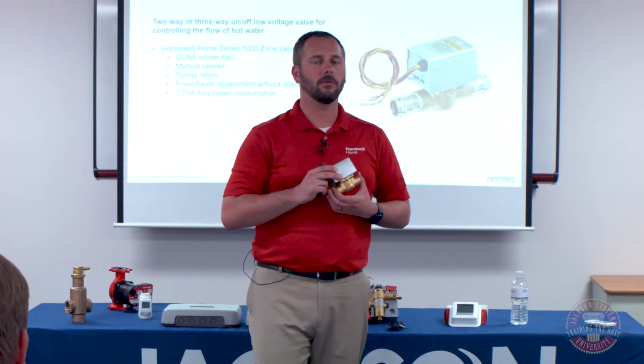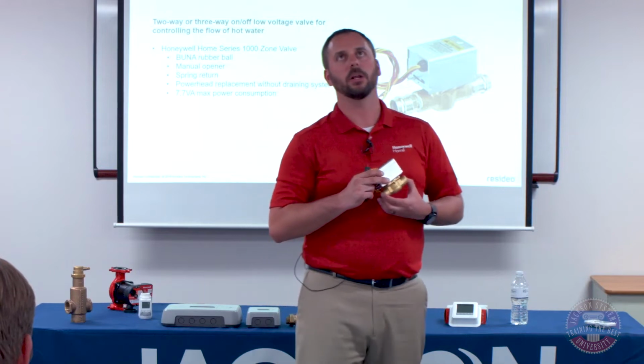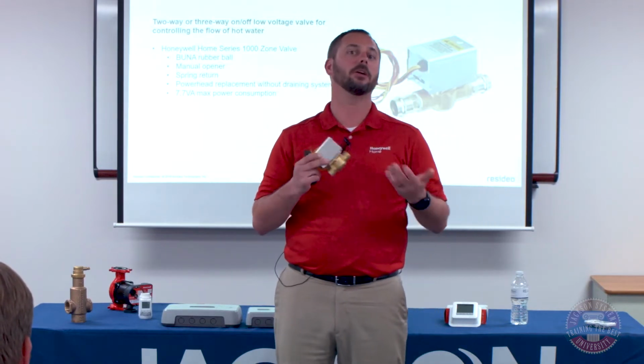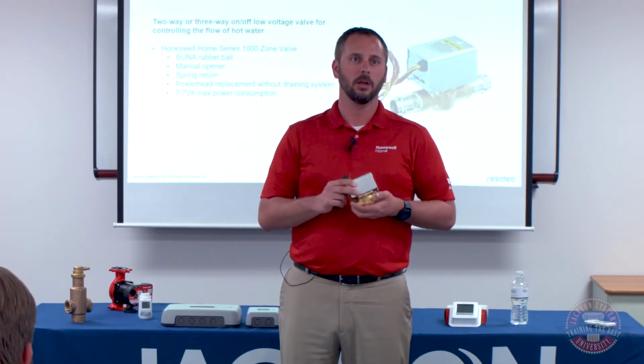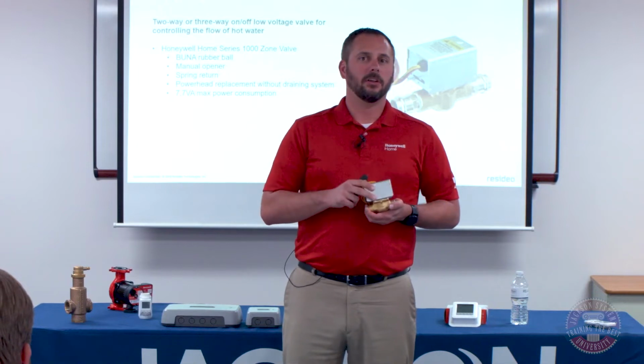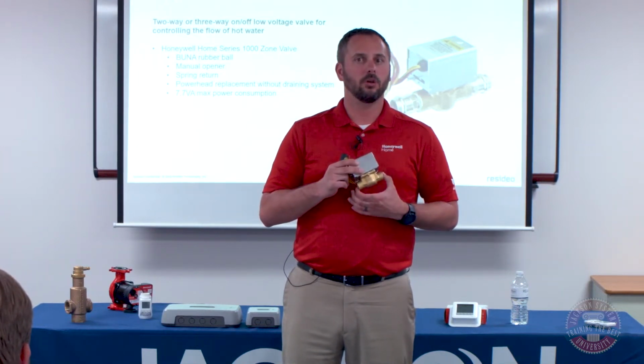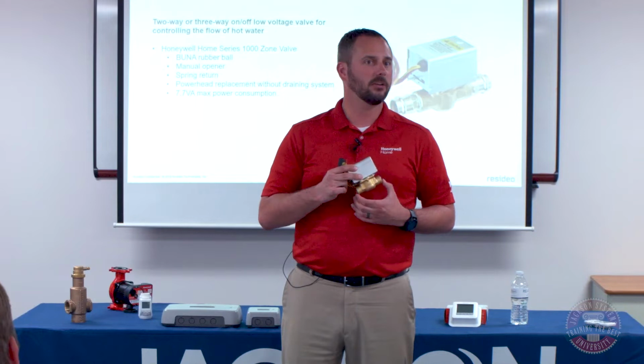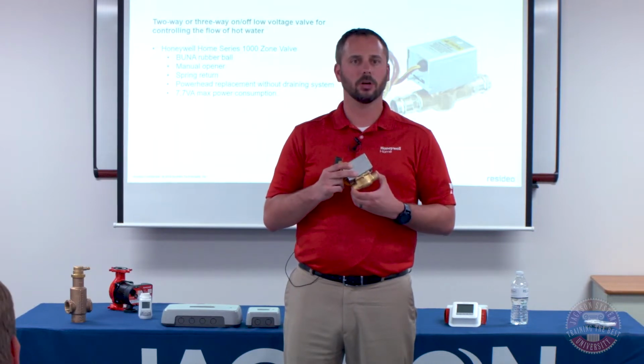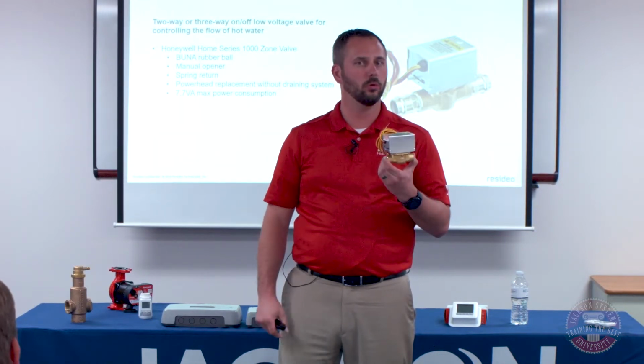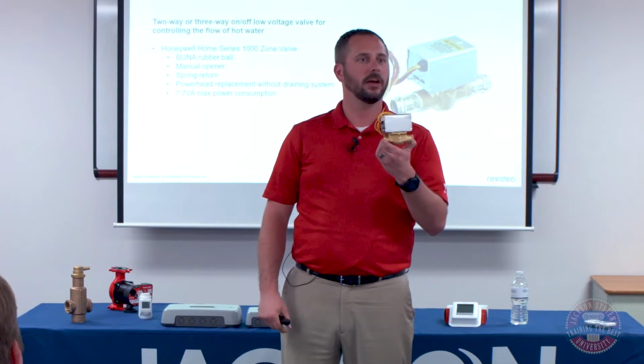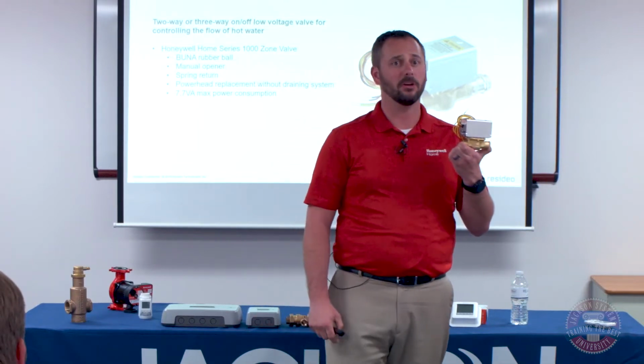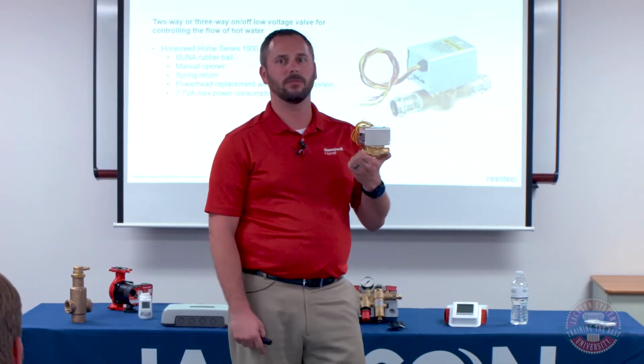When you put in heating systems, it needs to be closed loop, meaning there's no oxygen. I have seen systems where oxygenated tubing was used, so instead of PEX with an oxygen barrier, it was AquaPEX. You're constantly reintroducing oxygen molecules. It will corrode the inside of these valves, and you will get maybe 5 years out of them instead of the anticipated 15 to 20.